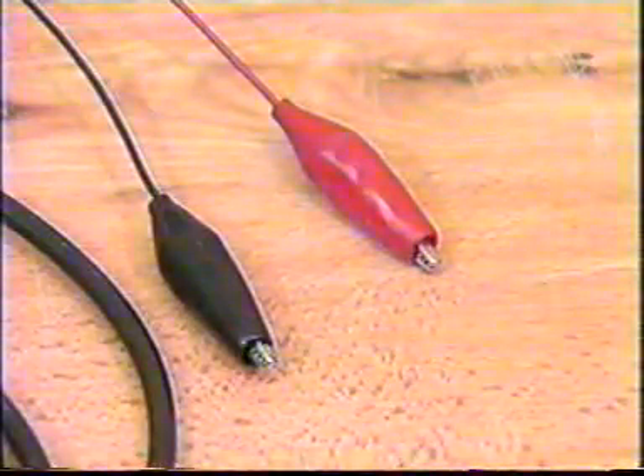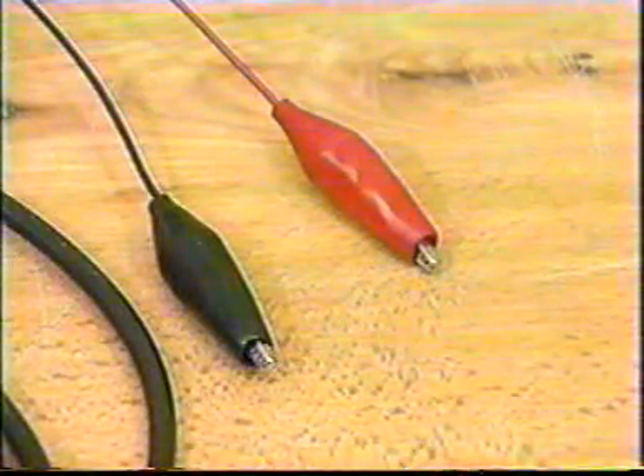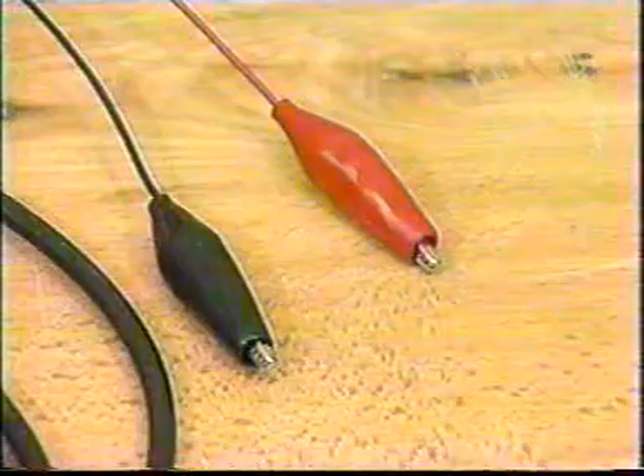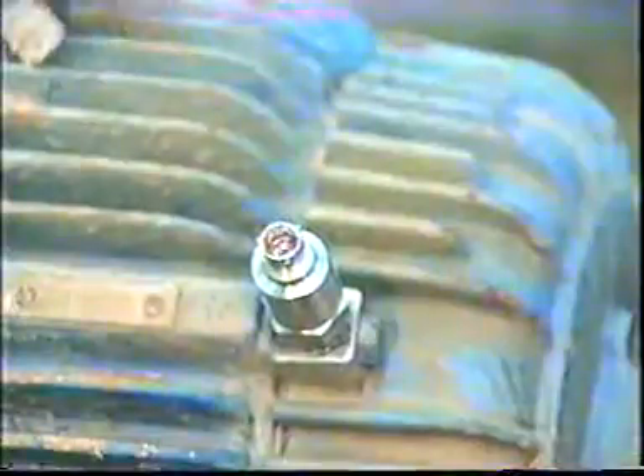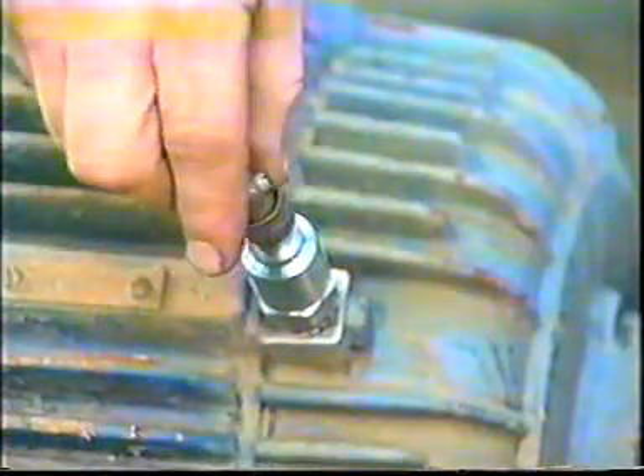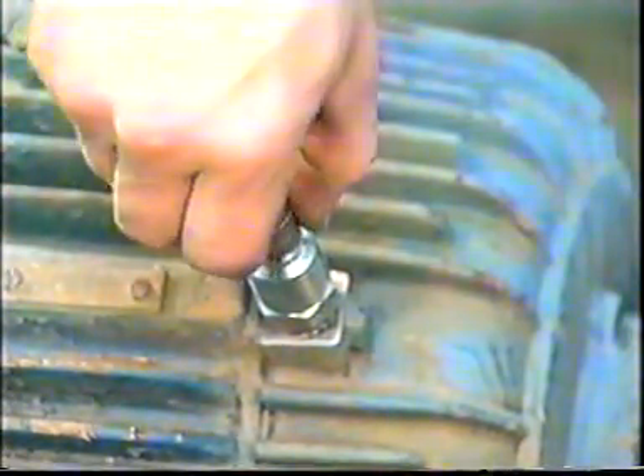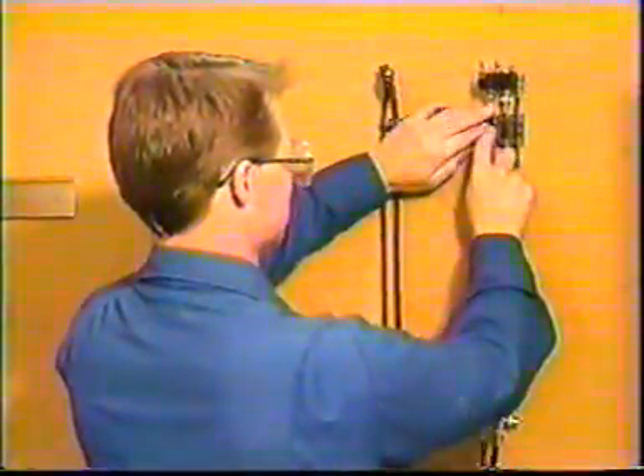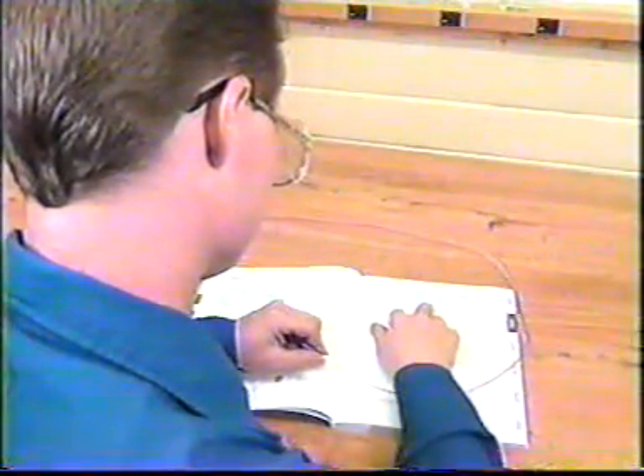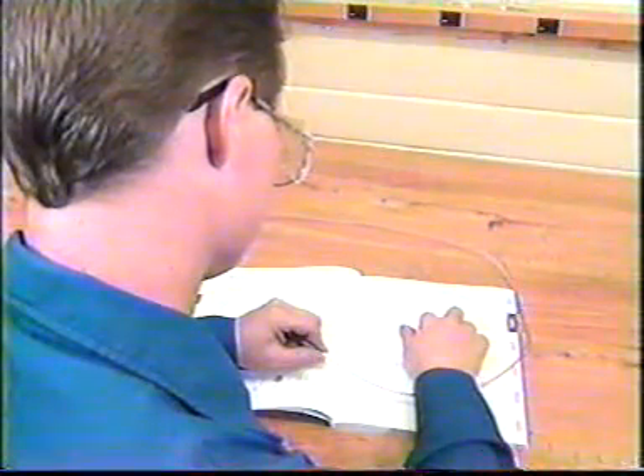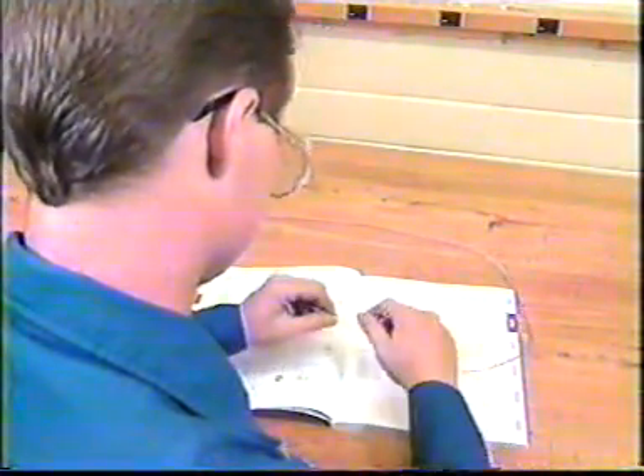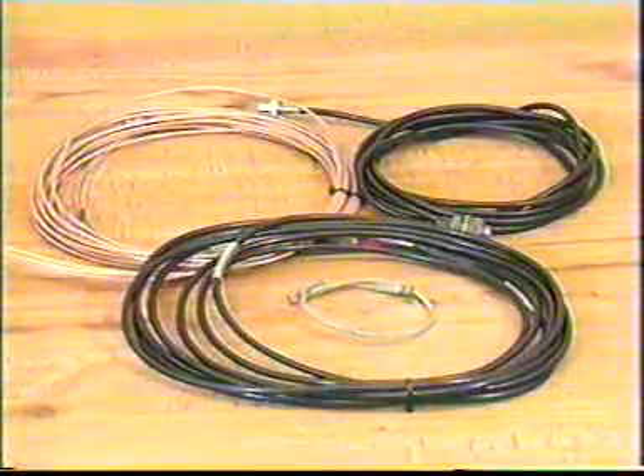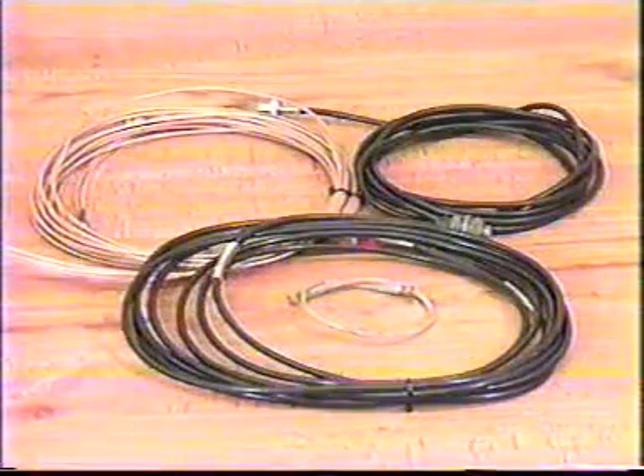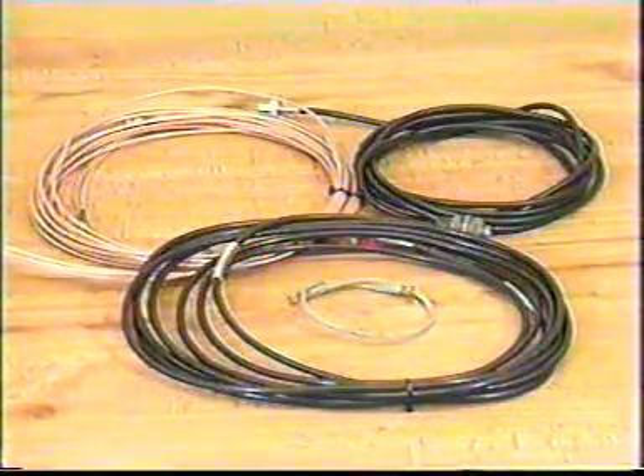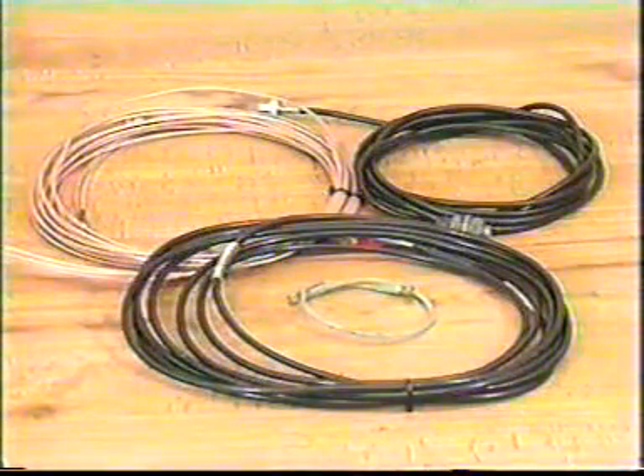Temporary connections, such as alligator clips, may also cause false signals. These clips may act as an antenna and pick up any stray electromagnetic field. Use only manufacturer-approved equipment. Do not substitute connections and cables to connect the test equipment. Store cables to protect them from crushing, moisture, and corrosion. If you need to replace cables, make sure to use an exact replacement. Check the part number. Even though cables look the same, there are differences. An incompatible cable will cause erroneous measurements. Using exact replacement cables, you ensure that impedance and cable capacitances are compatible with your system.